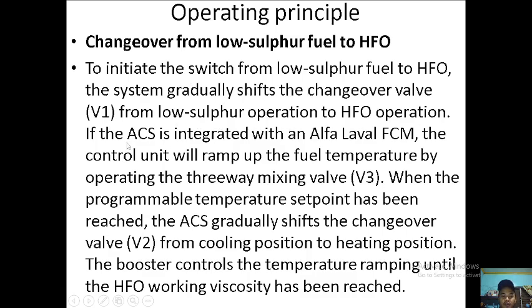If the ACS is integrated, the control unit will ramp up the fuel temperature, so the temperature will be increased by operating the three-way mixing valve. When the programmable temperature set point has been reached, the ACS gradually shifts the changeover valve from the cooling position to the heating position. The booster then controls the temperature ramping until the HFO working viscosity has been reached.